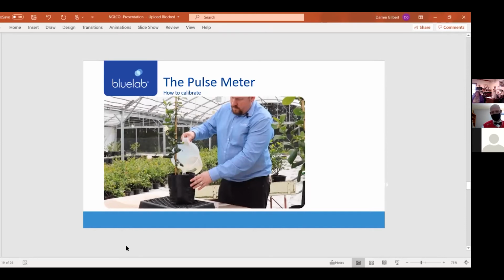The device, the Pulse, will hold up to 3,000 measurements before it needs to be downloaded. So when you get to 3,001, your very first measurement will go away. It will still keep everything going forward, but as you take the next reading, number 2 will disappear; take reading 3,003, and number 3 disappears, and so forth. It just keeps going unless you download that information to an Excel file.